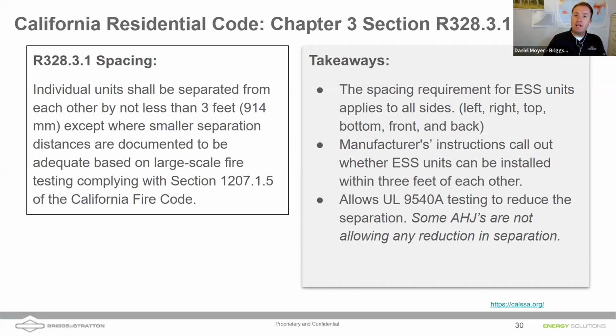It's 3 feet side to side, but also back to back. So picture a wall with a battery on one side and another on the other side—that needs 3 feet of separation. We don't see a lot of top-to-bottom battery installations. Our 6.6 battery is pretty thin, less than 2 feet wide but about 5 feet tall, and we don't stack those, partly because of needing access to wiring and the power button.